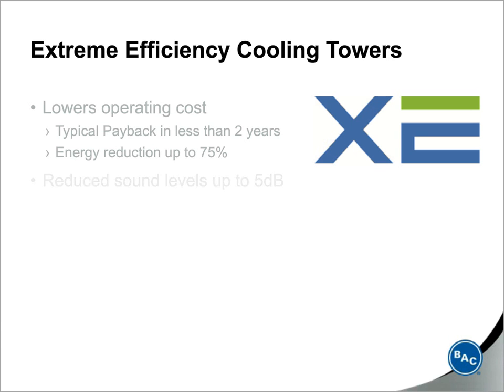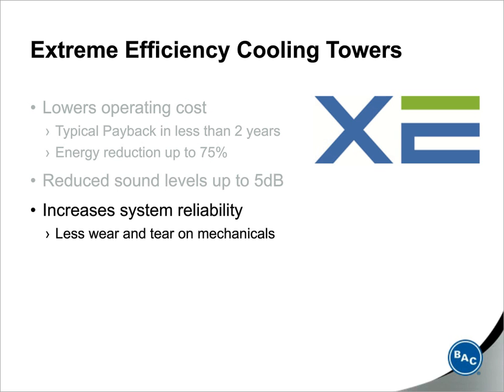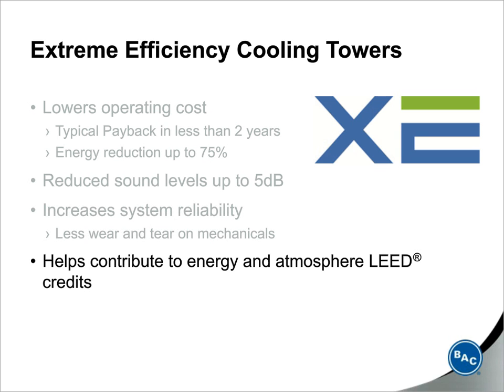And I mentioned it earlier in a previous design method, but since the fans in extreme efficiency towers are slower, since the tower is generally larger or more efficient, the fan can move slower, and you can reduce sound levels by as much as 5 decibels, which is pretty significant. These efficient models can also increase system reliability because there's going to be less wear on the mechanical moving components like your belts or your sheaves or your gears. And finally, these extreme efficiency towers can actually contribute to energy and atmosphere credits for LEED certification.